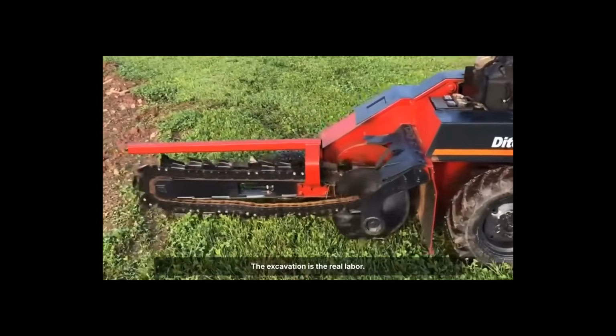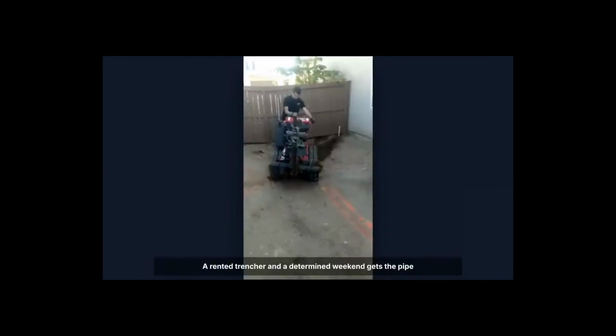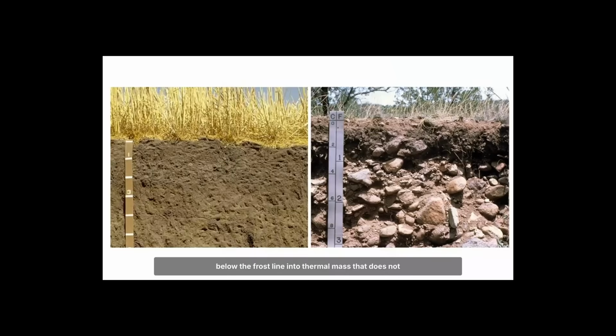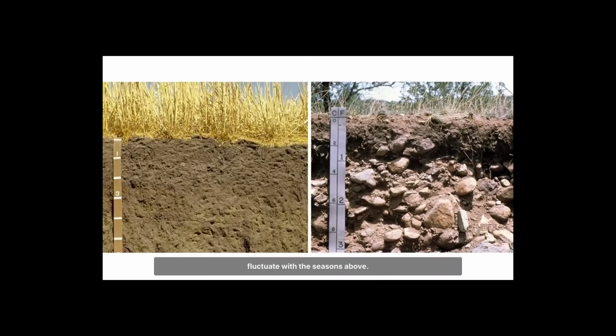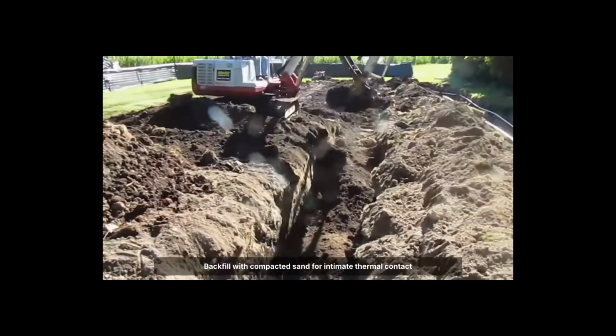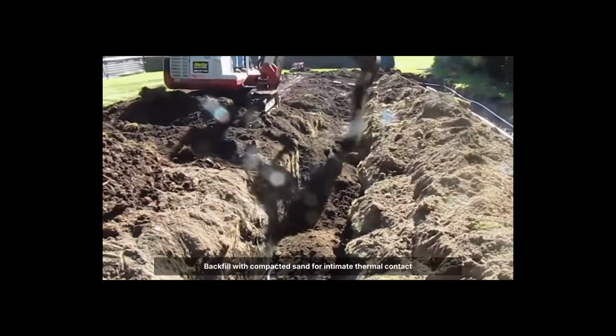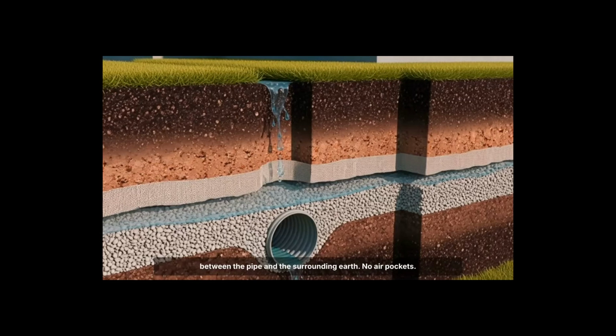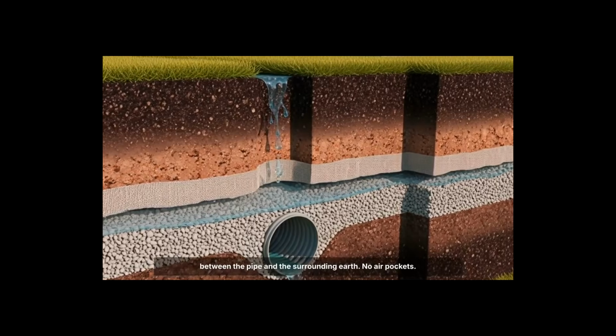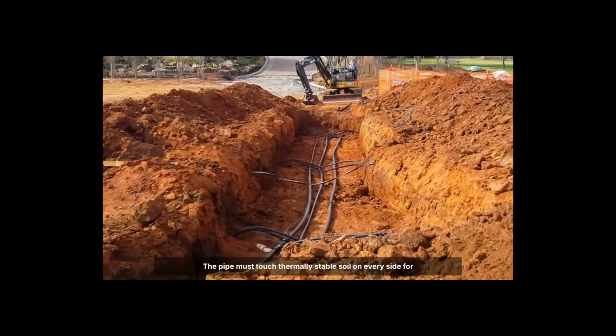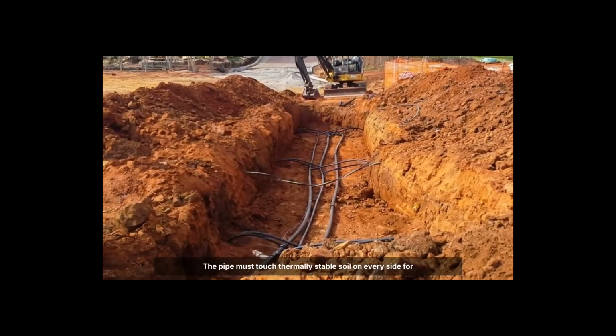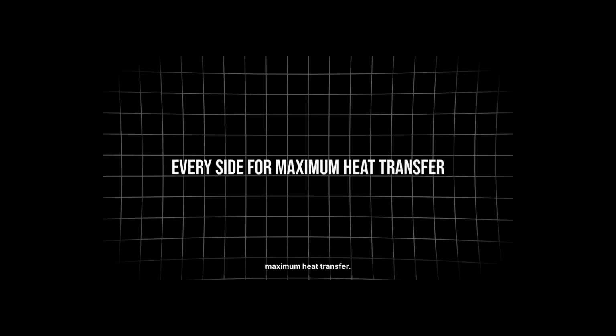The excavation is the real labor. A rented trencher and a determined weekend gets the pipe below the frost line into thermal mass that does not fluctuate with the seasons above. Backfill with compacted sand for intimate thermal contact between the pipe and the surrounding earth. No air pockets, no loose fill that will settle into voids over time. The pipe must touch thermally stable soil on every side for maximum heat transfer.